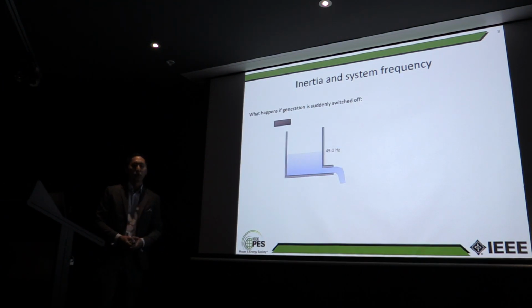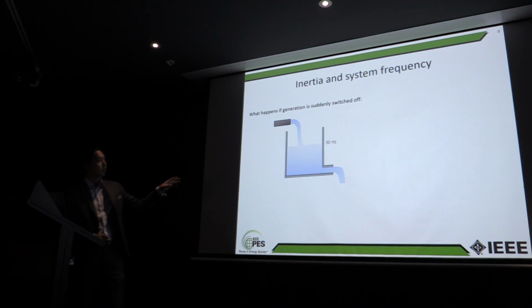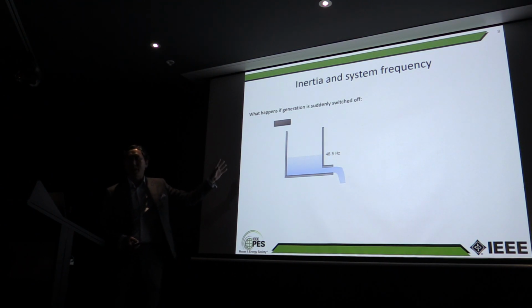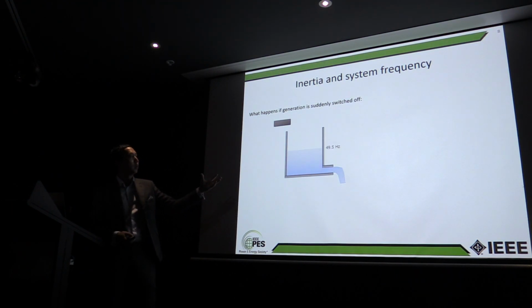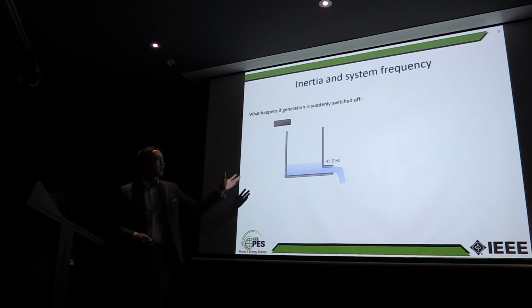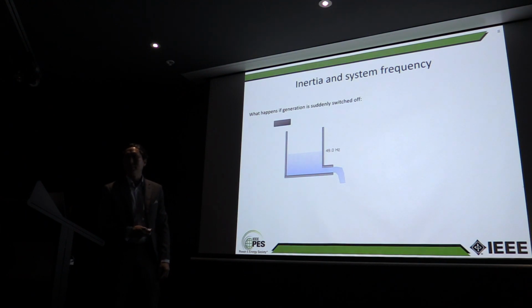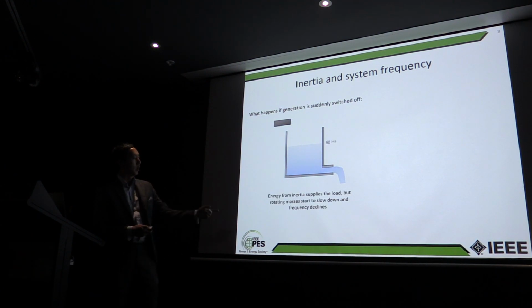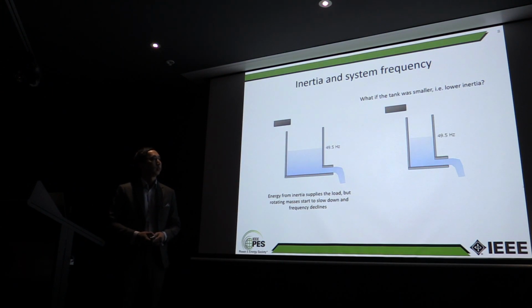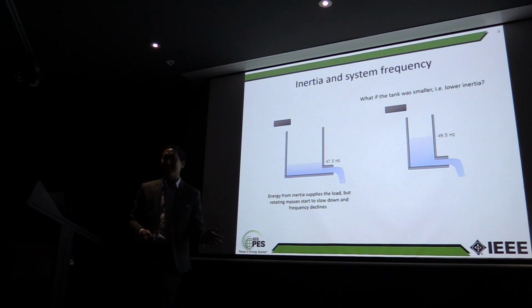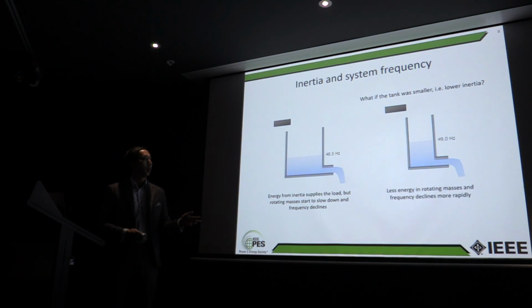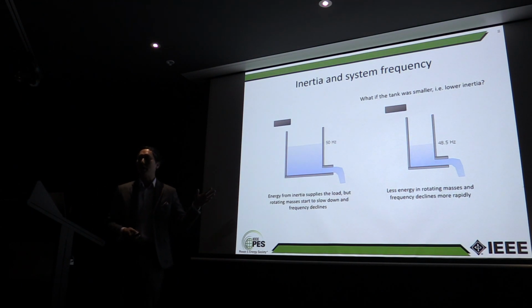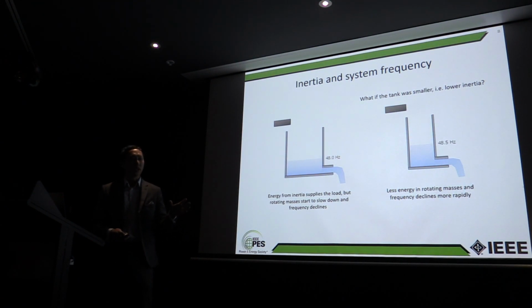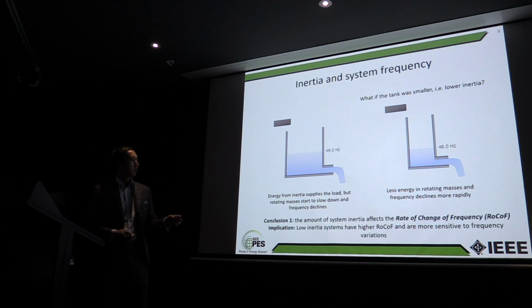So what happens if generation suddenly switches off? Inertia here is basically all the water in the tank, and that's the energy that's being used to supply the loads. The loads are still being supplied, but they're being supplied from rotating masses, and as a result, frequency starts dropping. Energy from inertia supplies load, we've talked about that. Now what happens if the tank was smaller? You can see here that it drains faster, and that is one of the key insights of inertia: the less inertia you have in the system, the less energy in the rotating masses, and frequency drops more rapidly. And the conclusion then is that the amount of system inertia affects the rate of change of frequency.